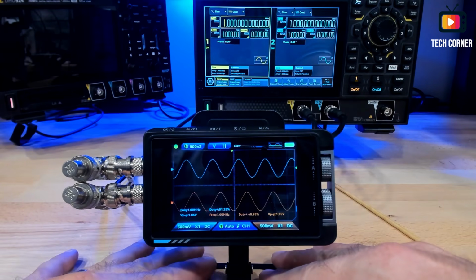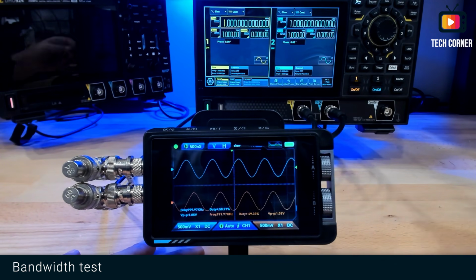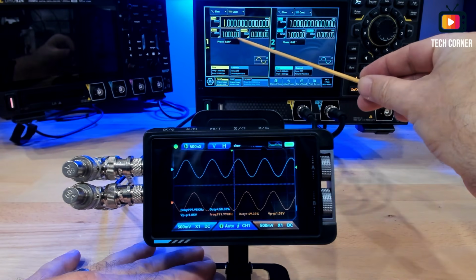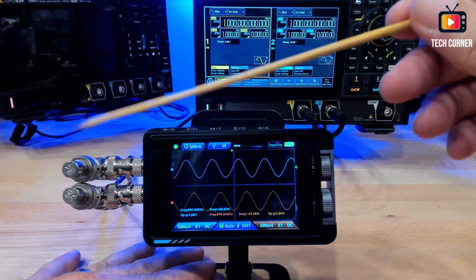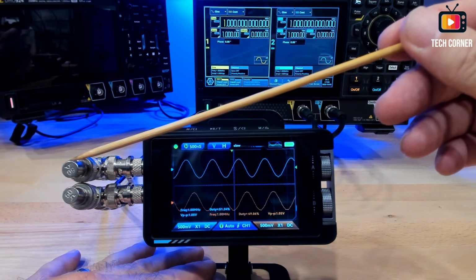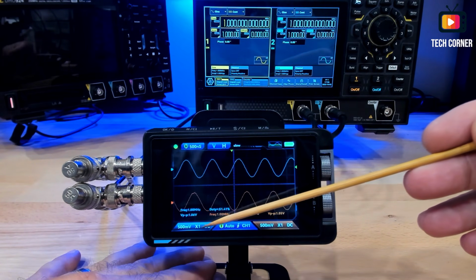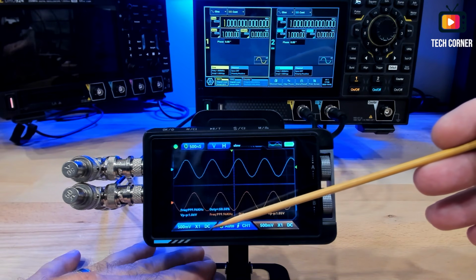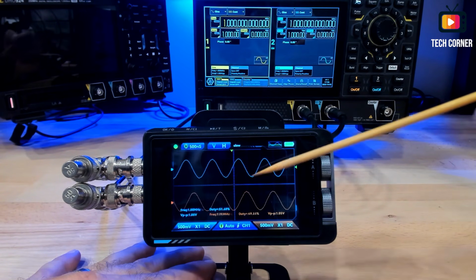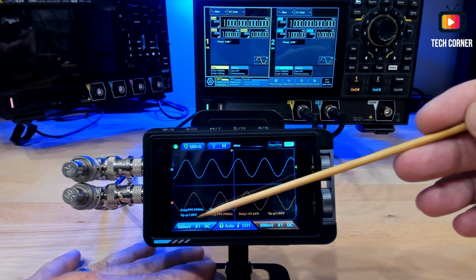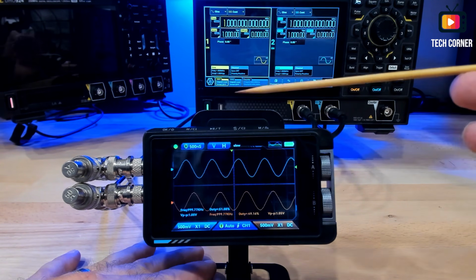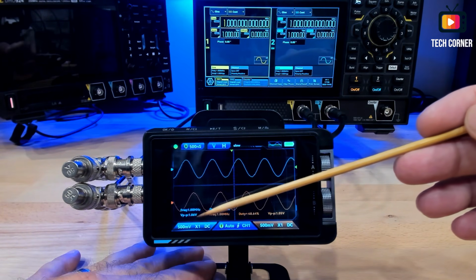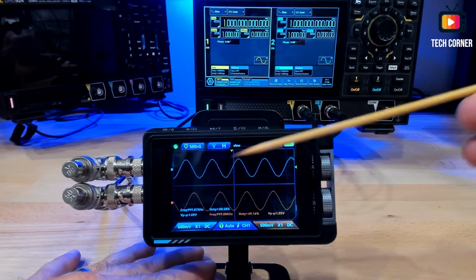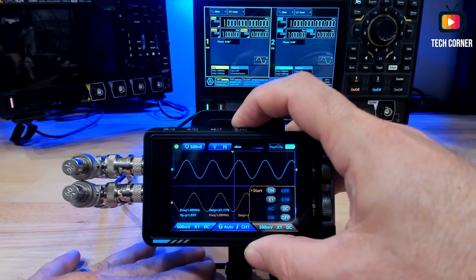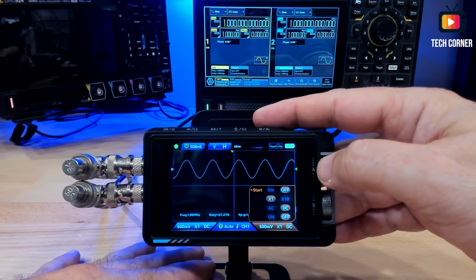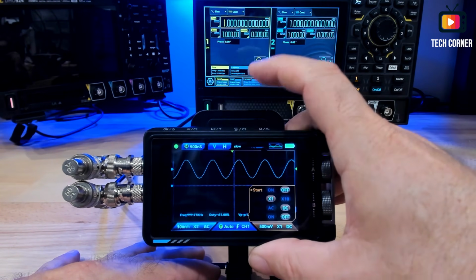So for the bandwidth test, I have my function generator already outputting a 1 MHz signal with a VPP of 1 volt. I'm using the BNC cables terminated by a 50 ohm terminator, and I will have for probe compensation the ×1 and the DC coupling. For the test, I will use the VPP as measurement. This value should not be lower than 710, 720 millivolts, around that, on both channels, but I will start first only with one channel. Let me just disconnect this one, okay, and do an auto again.